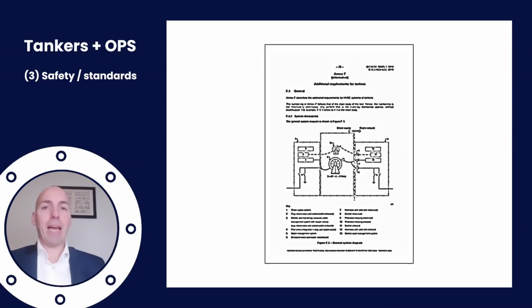Then safety and standards. Like I said, there is an annex in both IEC 80005-1 and -3 - 1 for high voltage and 3 for low voltage connection systems - that describes OPS for tankers, what to do and what not to do, basically prescribing it. But it doesn't prescribe it in that much detail. You still have a lot of leeway when designing these kinds of systems to accommodate ship-specific but also terminal-specific technical needs.